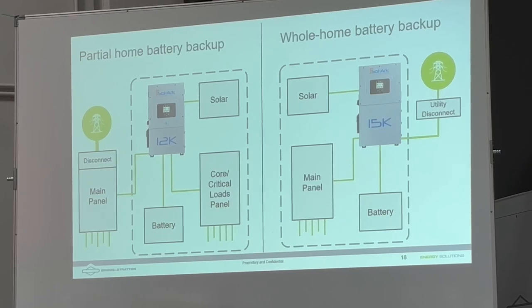I think that with the Powerwall 2, 6.5 kilowatts of power output, something like that. So Sol-Ark came out with this in 2019, maybe late 2018, the 15K with a 200 amp pass through, and now we're truly passing all the power from the grid through the inverter, backing up the entire main panel. So the main panel is off grid in a grid down situation, as opposed to the main panel being connected to the grid but not being powered.